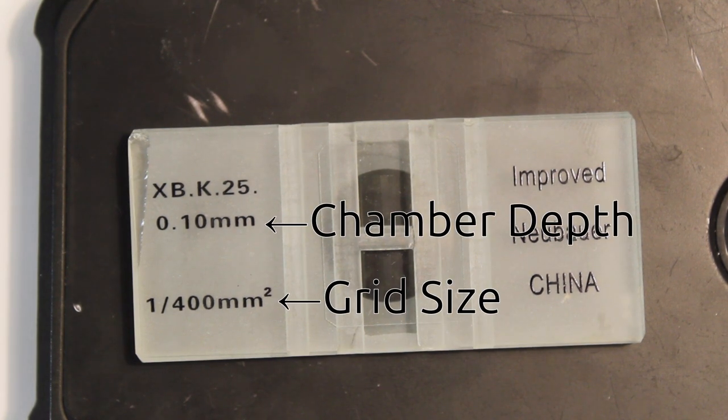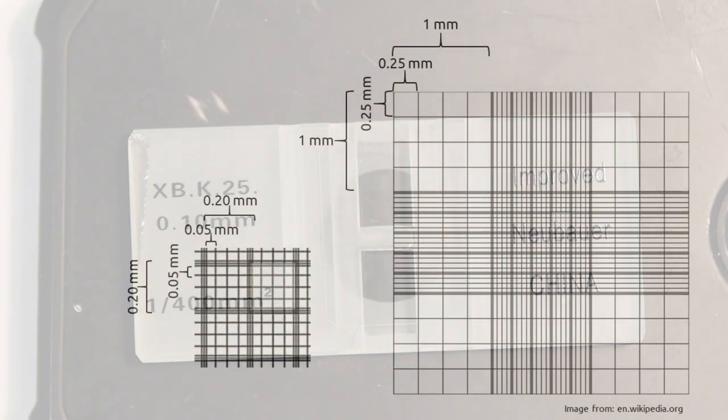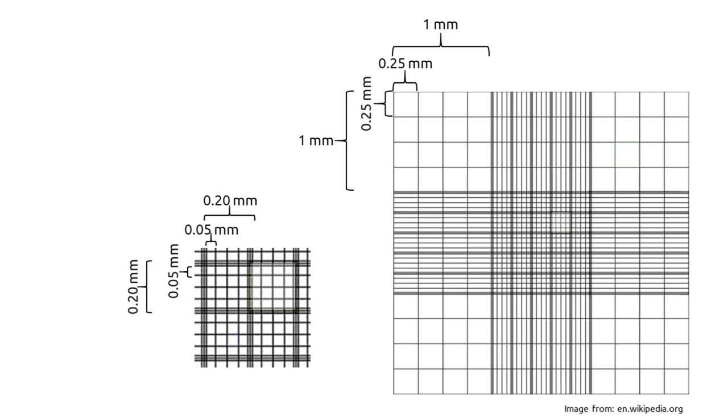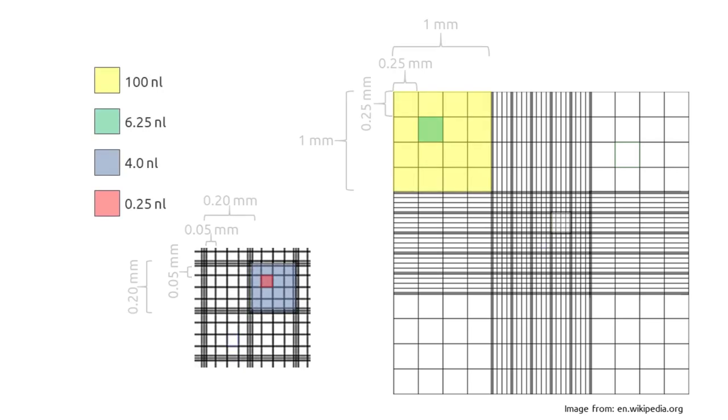Most hemocytometers use a standardized grid with a standardized height but always check the instructions that came with your hemocytometer to make sure that you're using the right calculations. The vast majority of hemocytometers have a one millimeter by one millimeter major grid region which is 0.1 millimeters deep. This means that 100 nanoliters of liquid will fill the area over the one millimeter by one millimeter grid region.